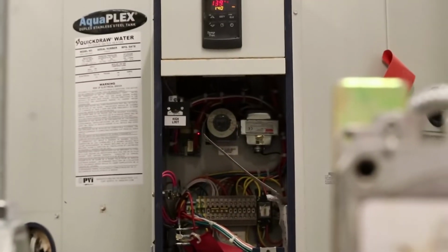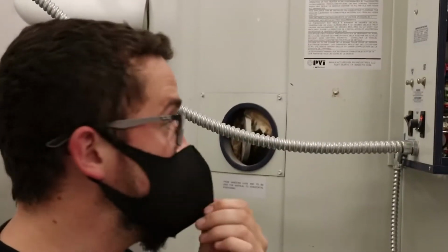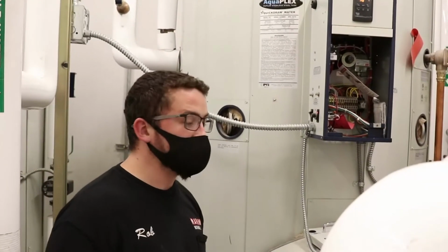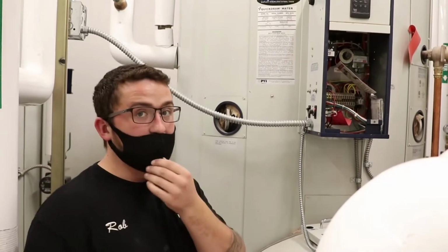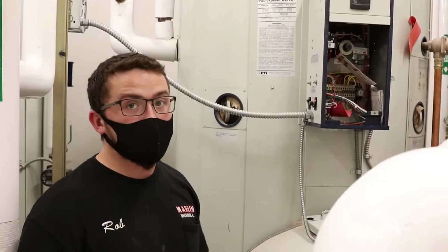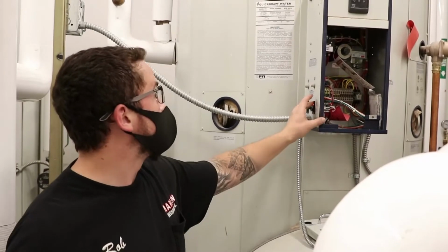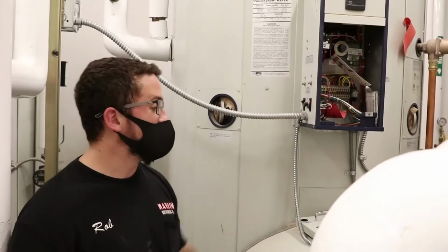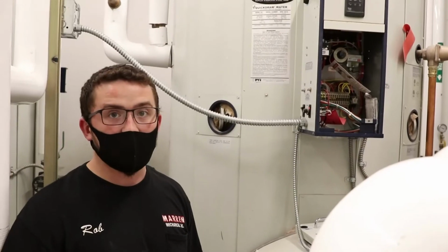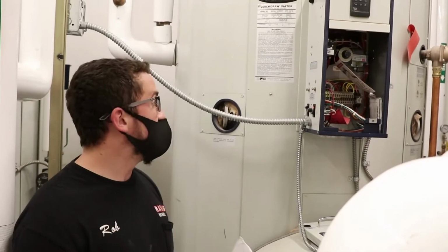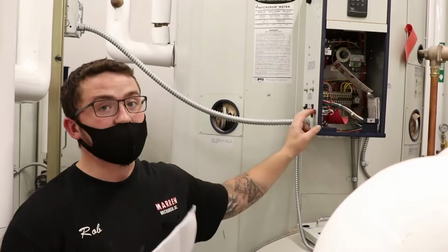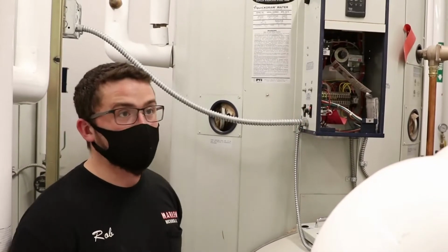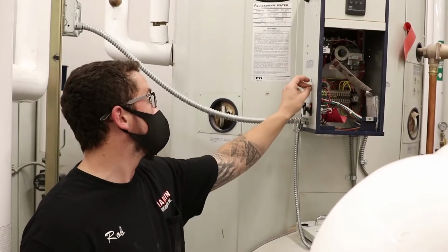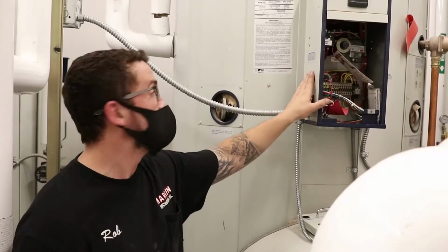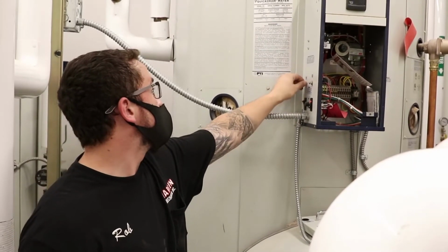That circuit board is connected to a probe that is threaded into the water side of the tank. If that probe should become fouled up or encapsulated in lime scale or any other type of sediment, that could cause the control to not work. It could either not work by constantly showing low water, or it could not work by never stopping operation of the heater, not recognizing that the water level has failed. So I would always try that test and reset function at least annually.